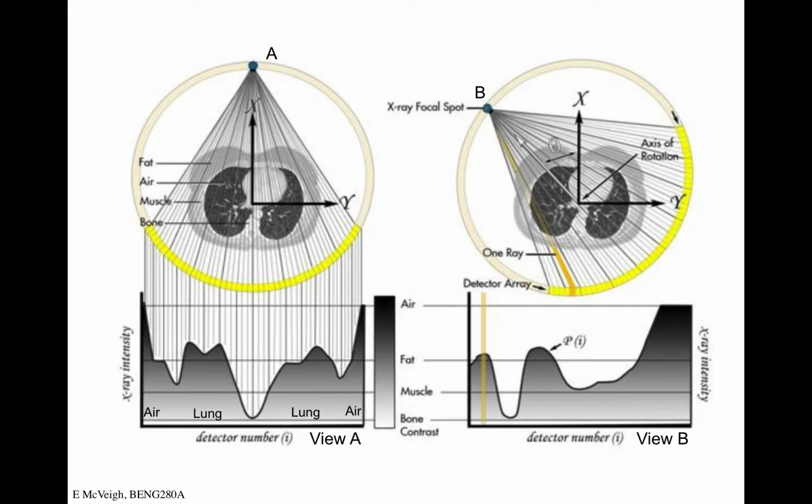Okay? There's some scaling, you have to do dynamic range adjustments and things like that, because some of the detectors will have an enormous signal and some will have a very low signal, and so there's a lot of encoding that goes on, but the basics are pretty simple.